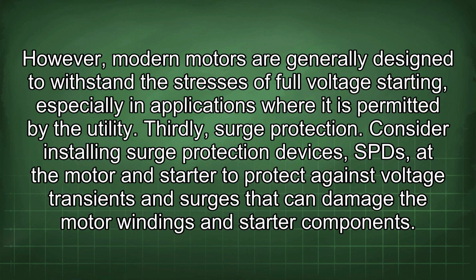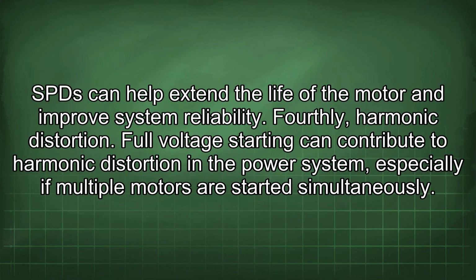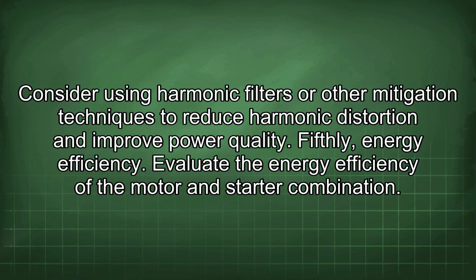Thirdly, surge protection. Consider installing surge protection devices, SPDs, at the motor and starter to protect against voltage transients and surges that can damage the motor windings and starter components. SPDs can help extend the life of the motor and improve system reliability. Fourthly, harmonic distortion. Full voltage starting can contribute to harmonic distortion in the power system, especially if multiple motors are started simultaneously. Consider using harmonic filters or other mitigation techniques to reduce harmonic distortion and improve power quality.